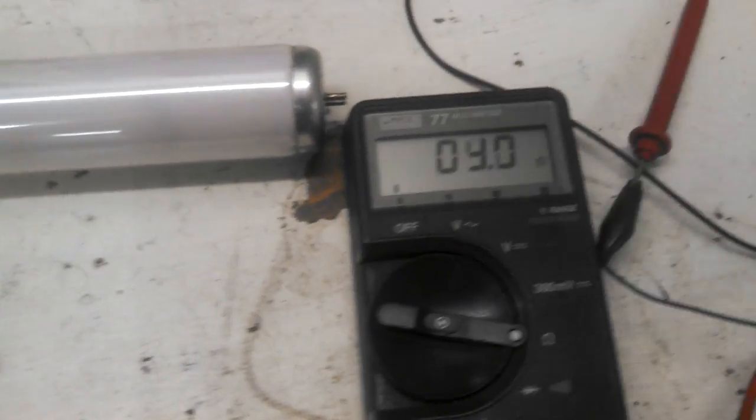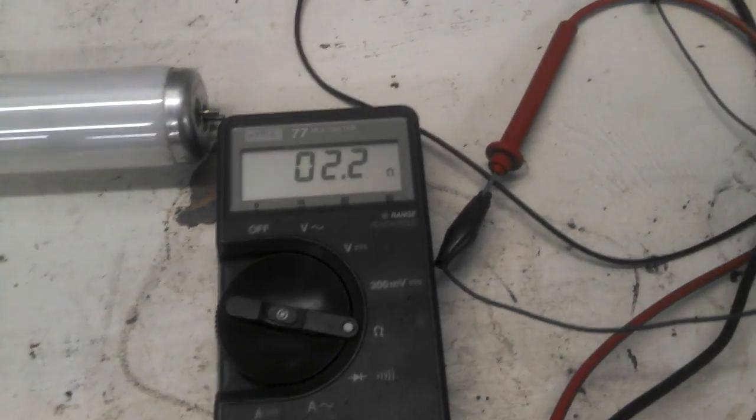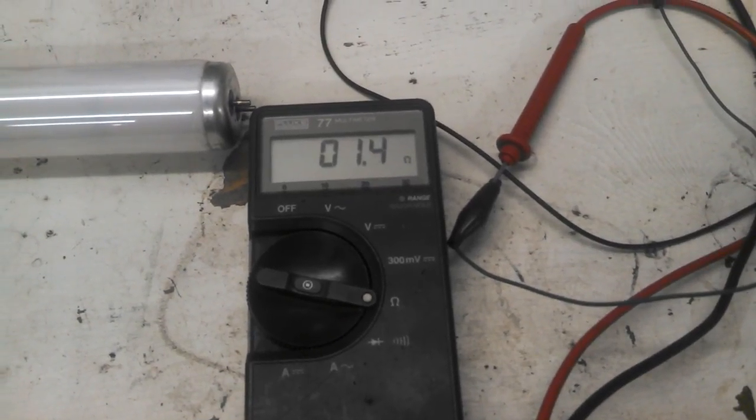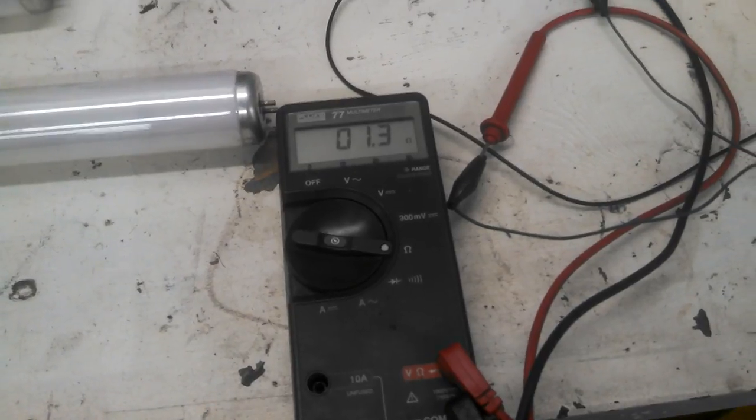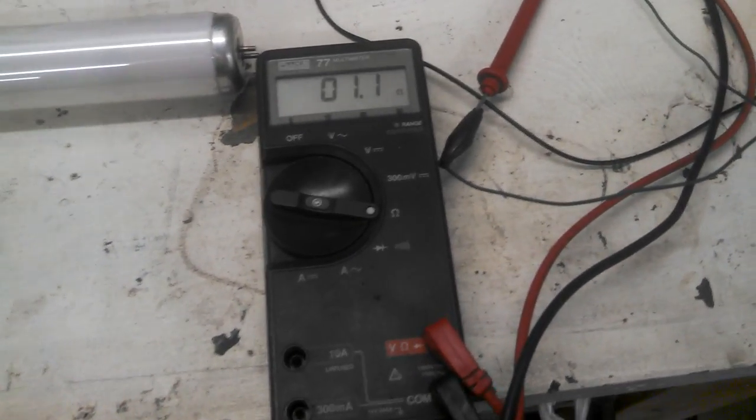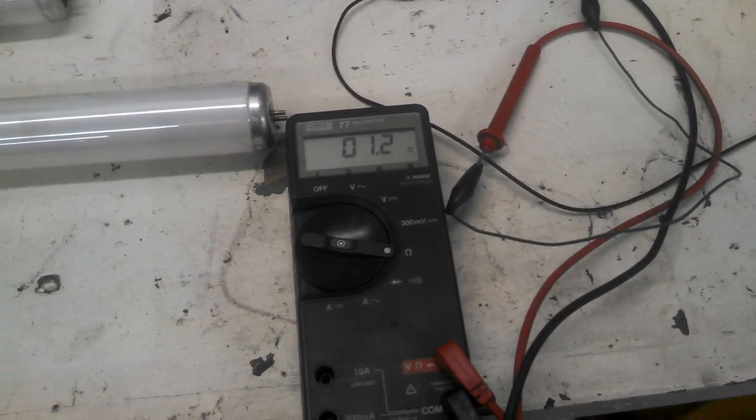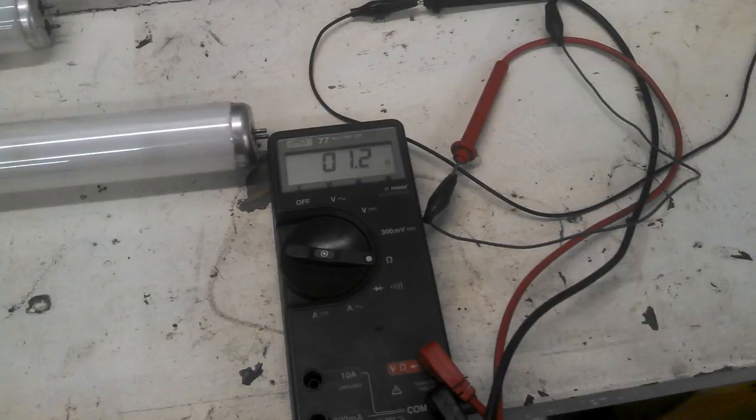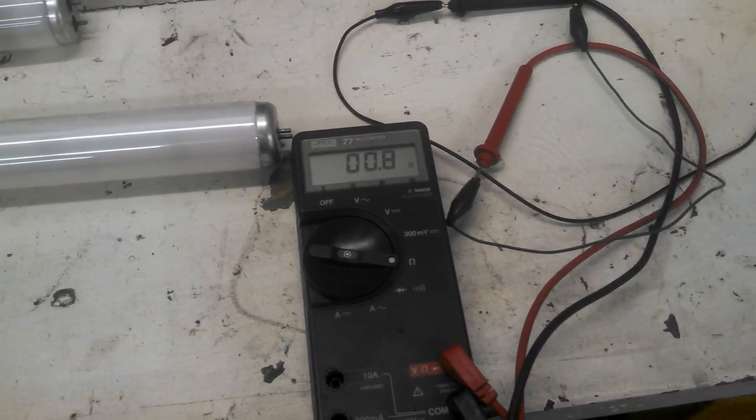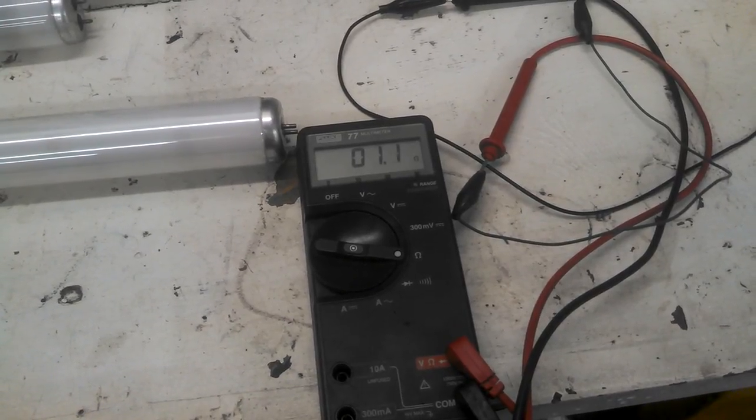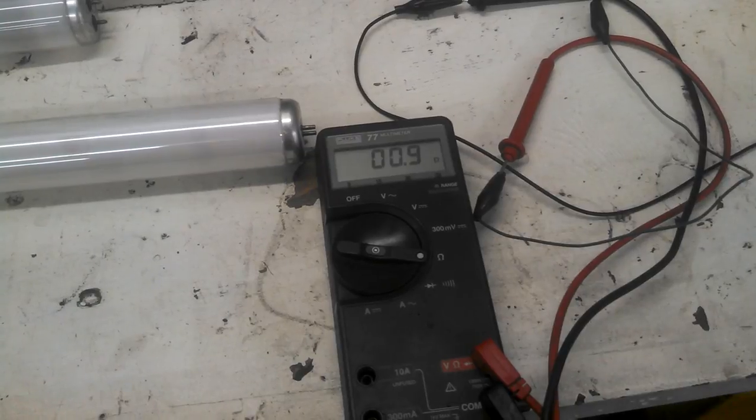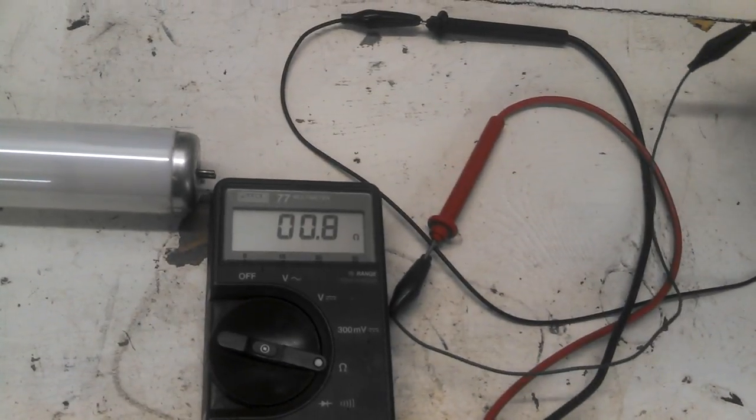Let's just clip the two alligator clips together just to make sure that we've got a good read here. That's reading. There must be a little corrosion on one of them because it's reading... it should be 0.00, but as the leads get old on both the meter and the clips, sometimes you don't get exactly zero. If I wait long enough it will go down to zero as you can see. You can see it's going to keep going. It'll get to zero.